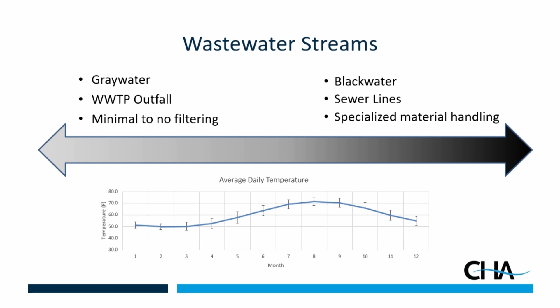These things aren't always where you need them to be, and that's one of the challenges. Another is how do you actually access these flows, because to put something through a heat exchanger it needs to be a pressurized flow. So how do I take my sewer flow, which is generally by gravity? If you can grab a force main that's already pressurized, you're golden, but most times you're looking at gravity flow, and you need something to interface those two together. In most cases, that's going to be some sort of wet well.